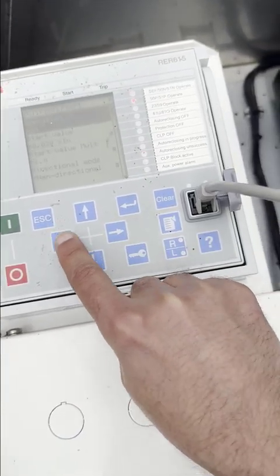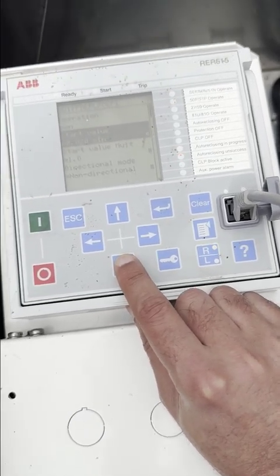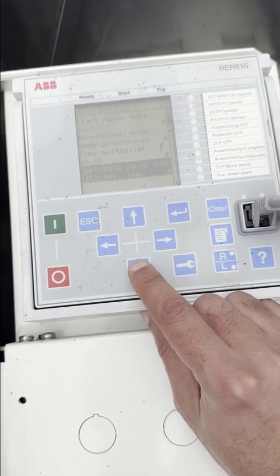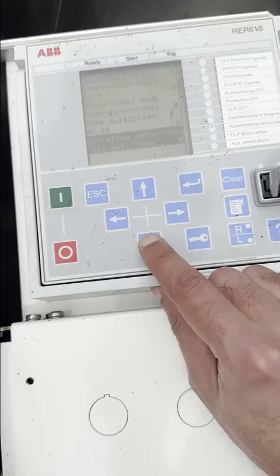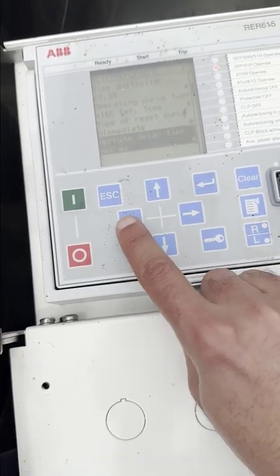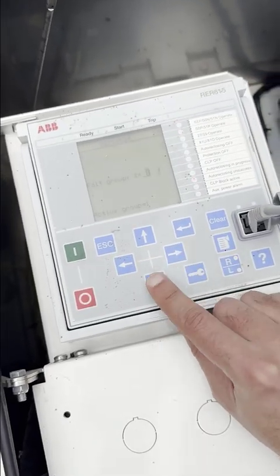Also for the earth fault, we have only one stage, which is 0.02 multiplied by IN, which means 12 ampere in primary, and it's non-directional. Time multiplier is 0.05, but the curve type is IEC definite time with operation time delay equal to 60 milliseconds. Then you can go also for the setting of the control function, which is a recloser function.